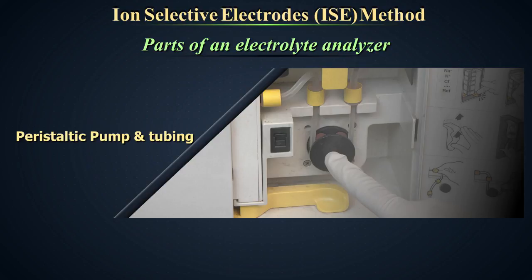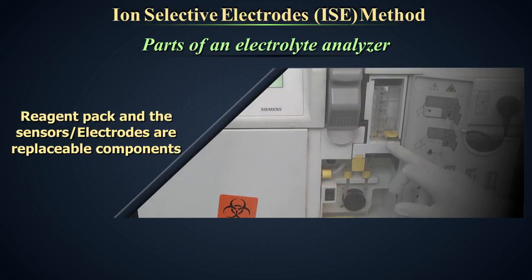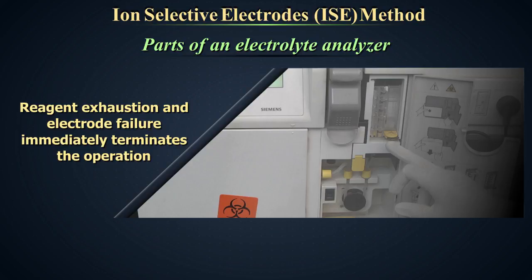Peristaltic pump and tubing. The reagent pack and the sensors are replaceable components of the instrument. Spares for both should always be kept as a backup as both are critical for running the samples. Reagent exhaustion or expiry and electrode failure will immediately terminate the operation. Hence, to ensure smooth functioning always keep these components in backup.